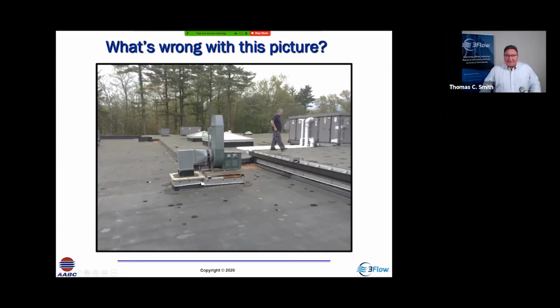The airflow is coming out of the building, and it's going to be expected to do a 90-degree turn directly into the fan. How many straight lengths of duct should you have before the fan inlet? What is the likelihood that you're getting a rotation of flow that's conducive to the fan operation? This square edge, I will guarantee there's no turning vanes in here.